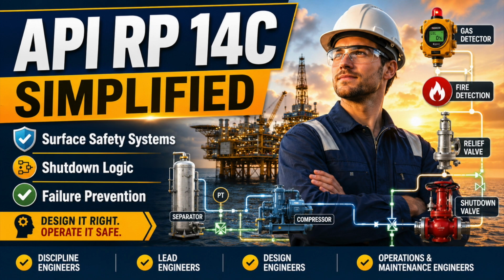You can install every pressure switch, shutdown valve, gas detector, fire detector, and relief device shown on a standard drawing, and still end up with an unsafe facility, because a safety system is not a collection of devices. It is a chain of decisions that must detect failure, stop hazardous energy, control released inventory, and prevent escalation before the process crosses the point of no return. That is the real engineering challenge behind offshore surface safety systems.